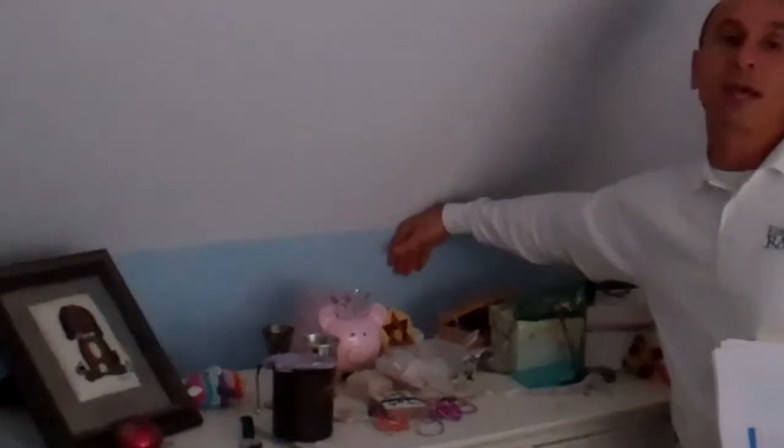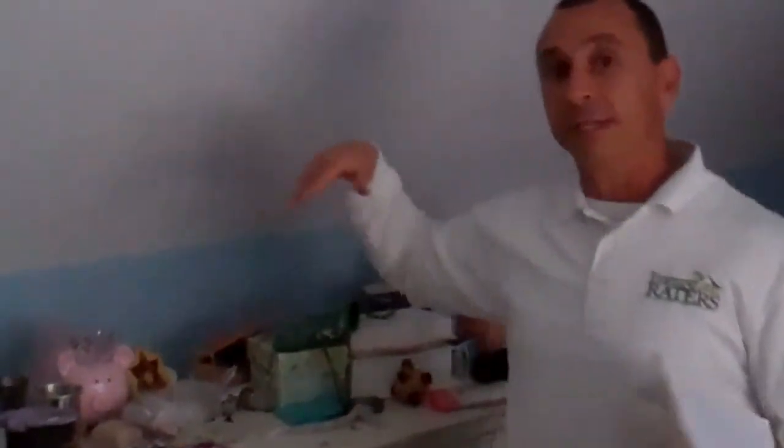Or we have these short walls in there. They're called knee walls. One of the things that happens is a lot of times you'll have insulation behind that drywall, but it won't have an air barrier on the opposite side. And insulation works best, especially if it's fiberglass or cellulose, when it's conditioned, or cocooned on all six sides, or touched on six sides. So top, bottom, left, right, inside, outside. That's how insulation will be most effective.